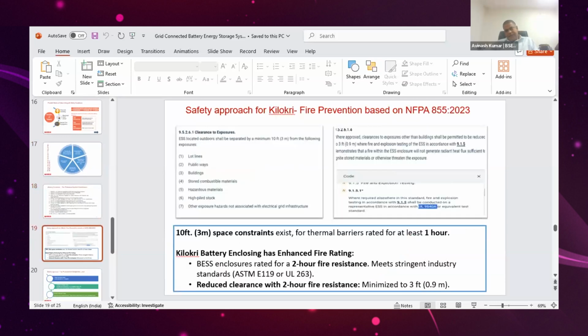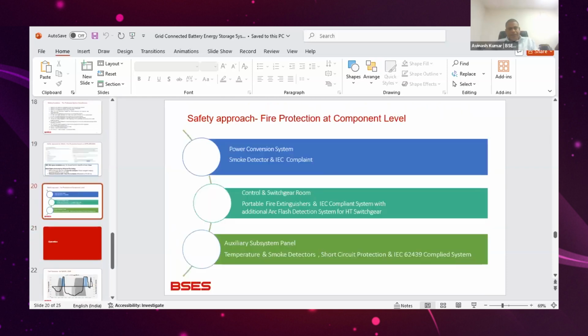Regarding the distance between containers, as per the standard there should be a minimum distance of 10 feet if 1 hour fire rated containers are used. But if 2 hour fire resistant containers are used, then this distance is reduced to 3 feet. We have a 2 hour fire rating for the container as well as the puff panel around the installation with a 2 hour fire rating. So we have maintained a 3 feet distance between the containers.